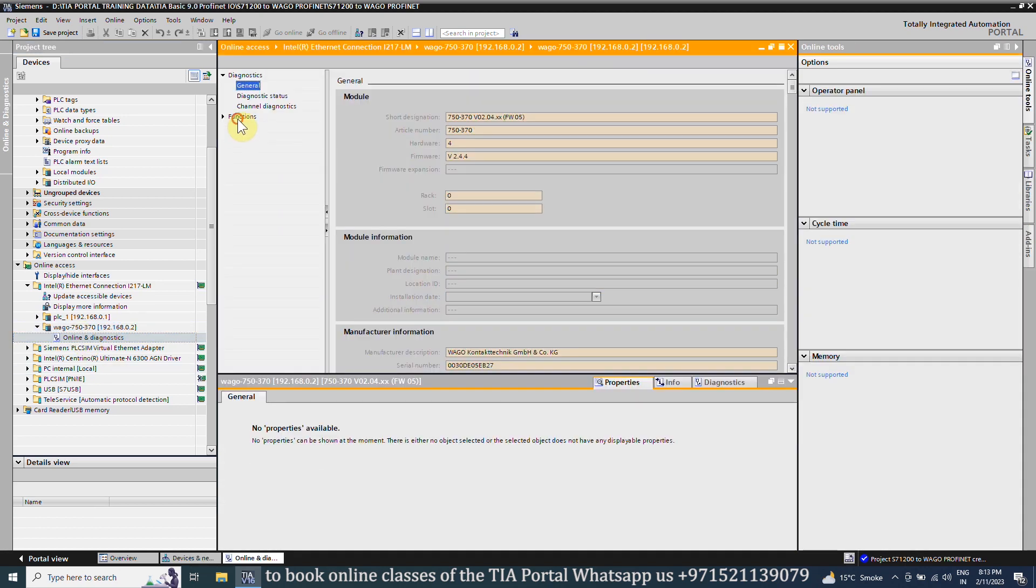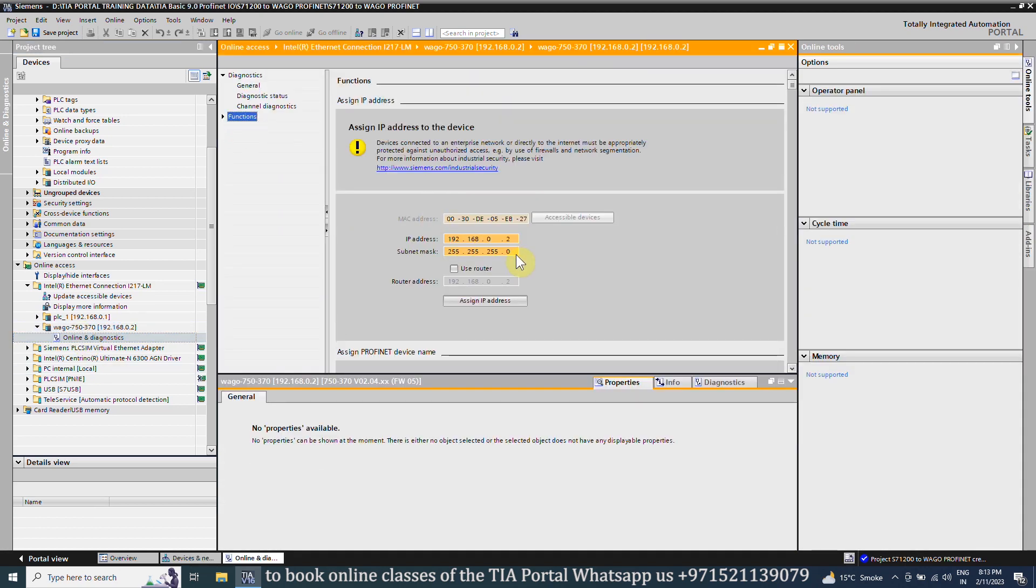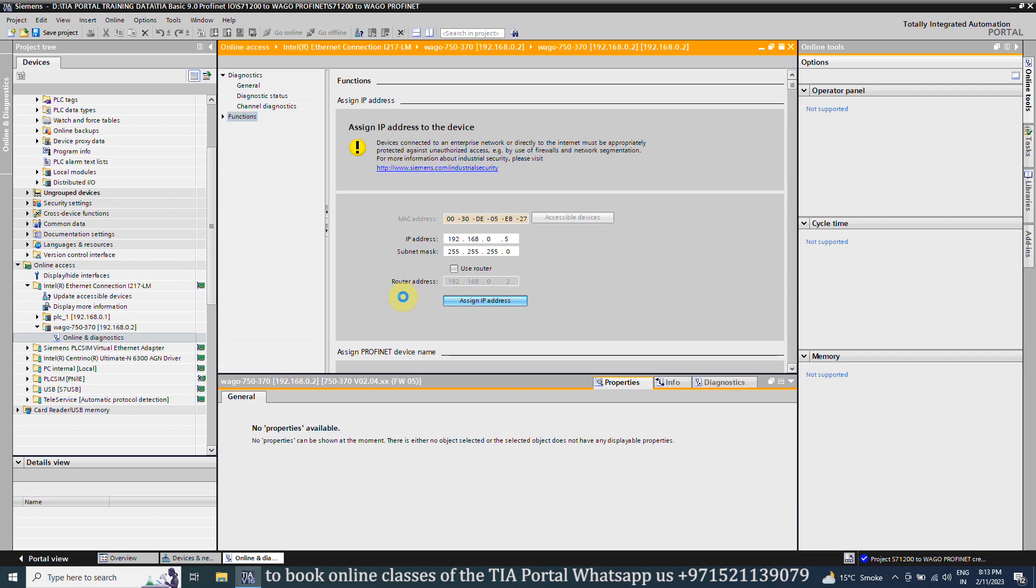Here we will select the WAGO module and open the online and diagnostic. Here in the function menu, we can see the IP address of the WAGO module. We can change it to 192.168.0.5 and click on the assign IP address button. It will assign the new IP address to the WAGO fieldbus coupler module.